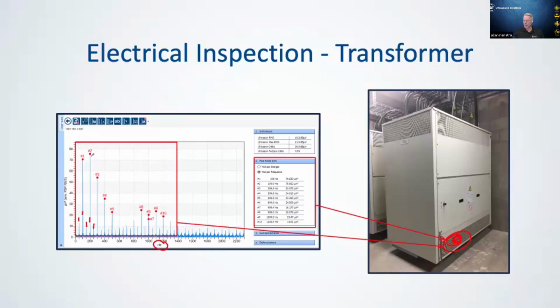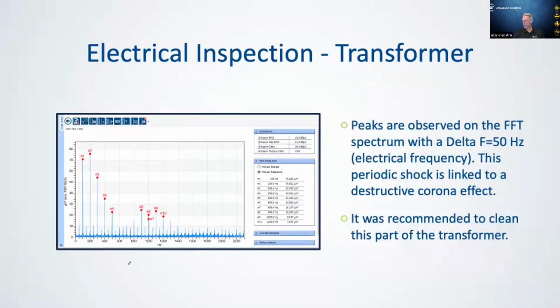But I can look at these repetition frequencies in the FFT, and I know right away that this is not arcing or tracking, but this is corona discharge, because the peaks are observed with a delta of 50. I kind of covered that, so I'm not going to repeat it again. The only thing I will emphasize is that this was determined to be destructive corona.